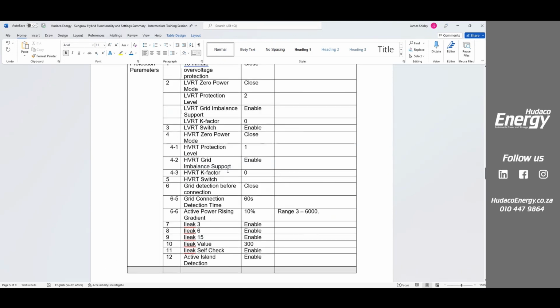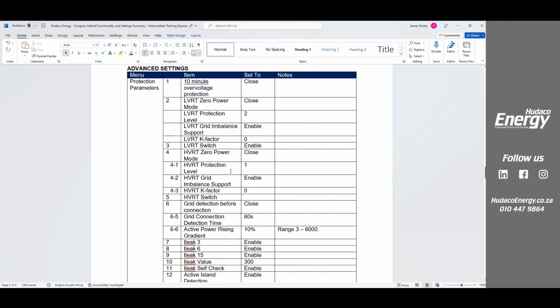You can manage them. At my own home, for example, my voltage often pushes up to 258 volts. So in other words, the national standard says 253 is the maximum. The moment we go above 253 volts, the inverter actually disconnects because it's required to. It's not a fault with the inverter. It's an NRS setting. So we've actually had to change not only my protection level, but also my ride through with my high voltage ride through switch, so that mine only kicks in at 260 volts now. So when I go up to 258 volts, the system says, well, it's fine.